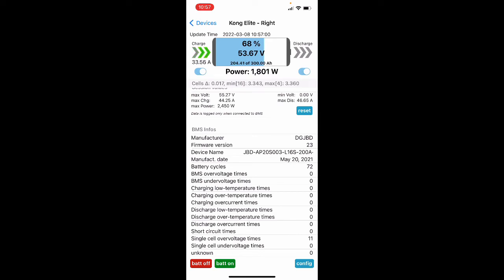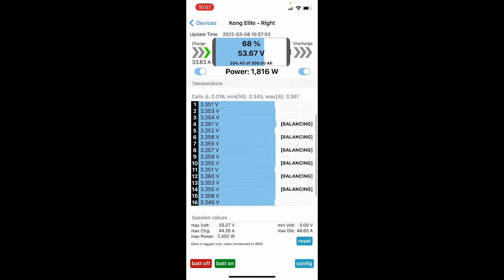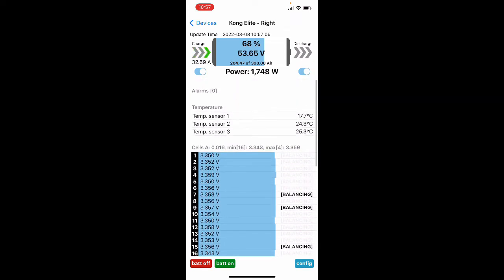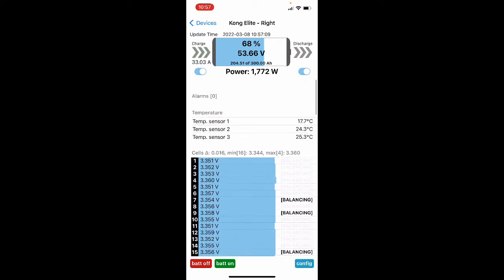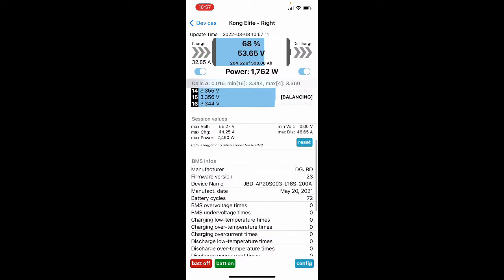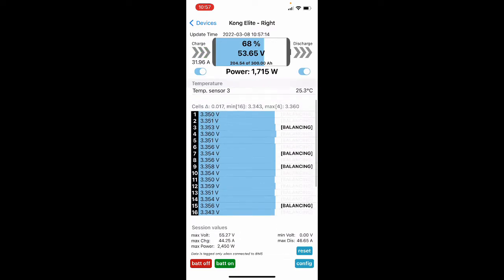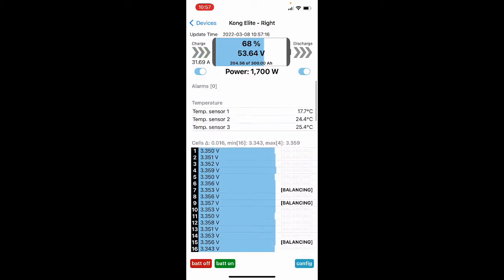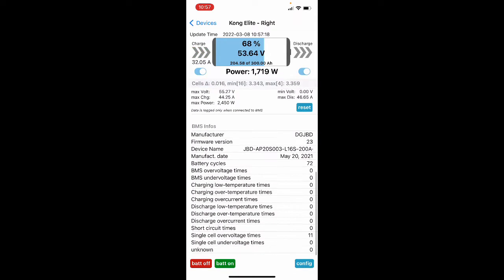You've got one cell going above 3.8 and then it shuts down its charging. When that happens, the SMAs fault and you lose power, then it does come back on its own, but it's not good to have those power glitches. It's sort of like a brownout - well, not a brownout, it's a hard shutdown and then a restart.